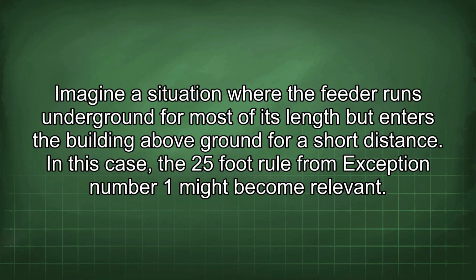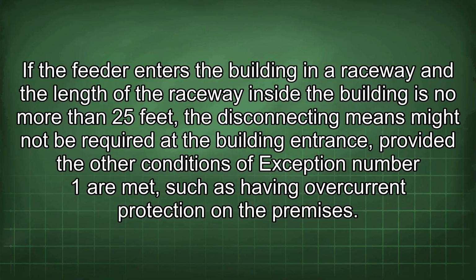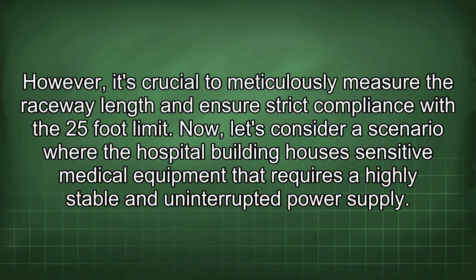In this case, the 25-foot rule from exception number 1 might become relevant. If the feeder enters the building in a raceway and the length of the raceway inside the building is no more than 25 feet, the disconnecting means might not be required at the building entrance, provided the other conditions of exception number 1 are met, such as having overcurrent protection on the premises. However, it's crucial to meticulously measure the raceway length and ensure strict compliance with the 25-foot limit.